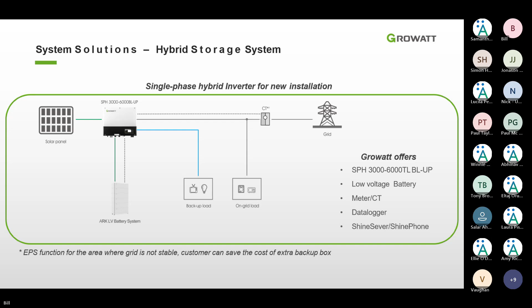Here's the multiple storage inverters working in parallel. So one inverter comes with like 10 kilowatt DC input and 6 kilowatt output. But I know in the UK sometimes it's not enough for single phase. But you can even parallel it up to 3. If, like I said, there are export limiting requirements, then up to 3 inverters with 6 kilowatt would be able to parallel. And each of the inverters you can connect its own panels and own battery. So that will be able to support like 30 kilowatt DC.